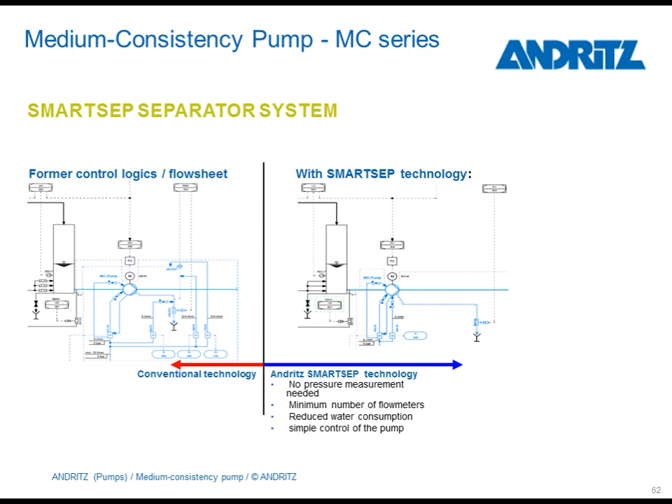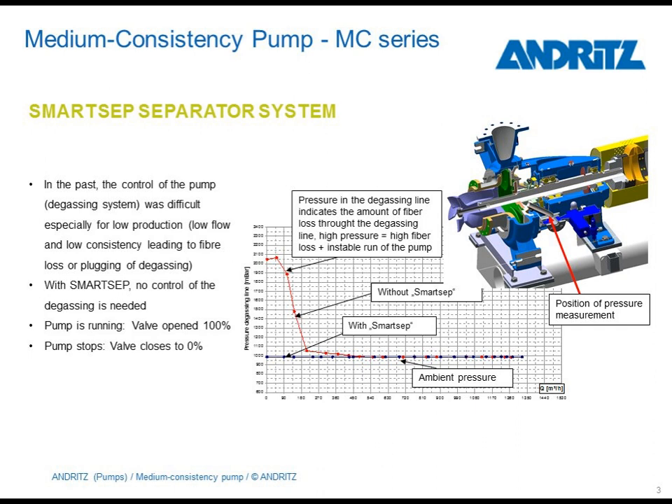This picture shows how much simpler the control logic became compared to conventional technology. A higher pressure in the degassing line indicates fibers flowing through the pipe, meaning the risk of plugging of the degassing line increases. So you always need continuous flushing of the piping with water. Without any fibers, no flushing is needed, and no water needs to be wasted for this purpose. This diagram shows how the SMARTSEP system improved the situation in the degassing line.